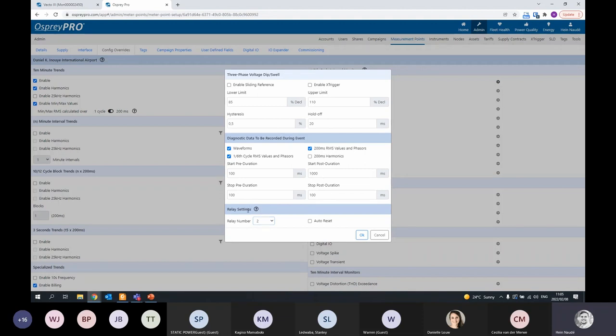There are 2 ways that these relays can operate. The first is auto reset, meaning, let's say there's a dip — the moment the dip starts, the relay closes, and when the dip stops, the relay opens again. Now if you disable auto reset, when there's a dip the relay will close and stay closed until you manually reset it or until the next dip happens. That can be used, for example, if you want to use it as a counter to count the number of events — it triggers, and then triggers again when there's a next dip. So that's how the relays can operate, the 2 ways.